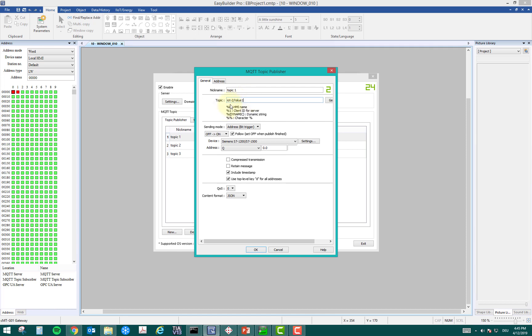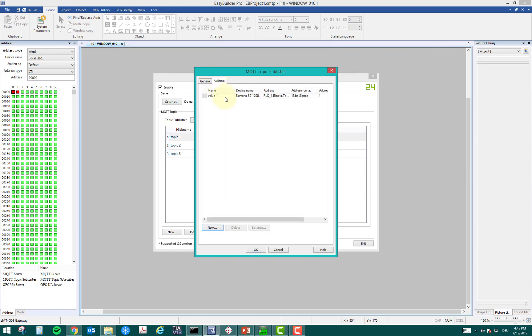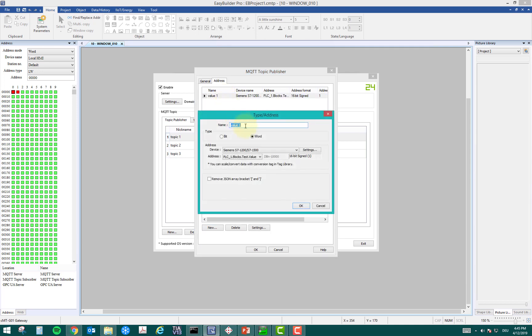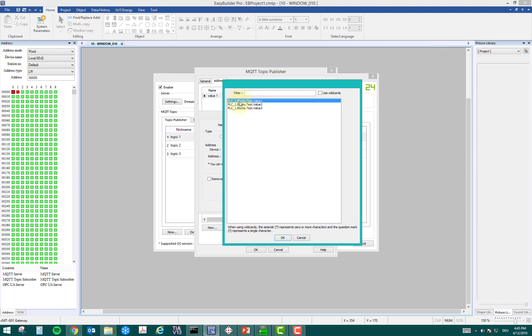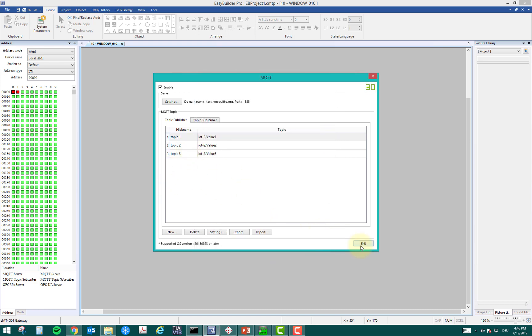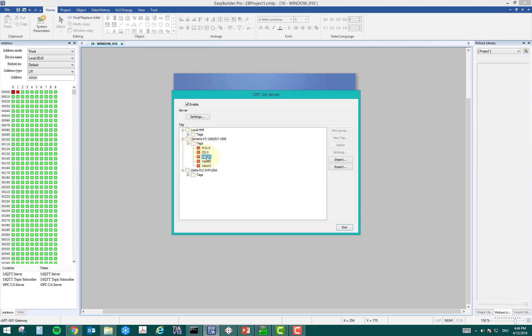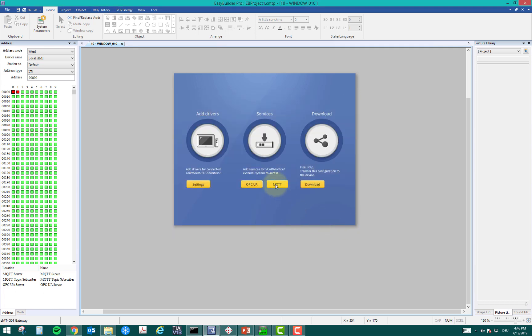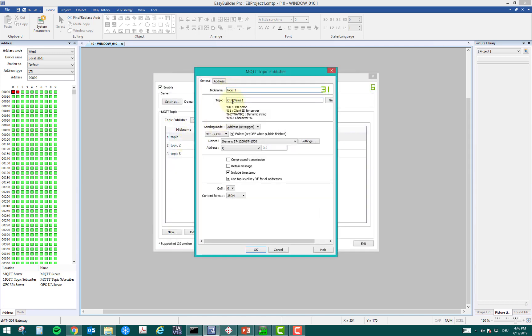I chose the topic IoT-2/value1. Now this topic is just a string as of now. The topic gets its value when you go to the address field and add a tag. Here I added a tag called value1, which is coming from device S7-1200, and the tag is value1 PLC1 block test dot value1. This is an OPC tag. If I go back, close MQTT, and go to OPC, you can see value1 — this is the tag we defined in previous lessons. I'm linking this OPC tag value1 to topic1.